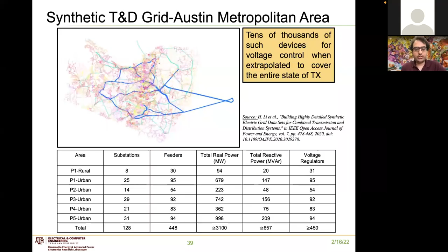It's possible that many feeders have more than one regulator, especially longer radial feeders that require more regulators to control voltage. When we extrapolate this to cover the entire state of Texas, we're potentially looking at tens of thousands of these mechanical devices that are prone to failure as we keep adding more distributed generation.